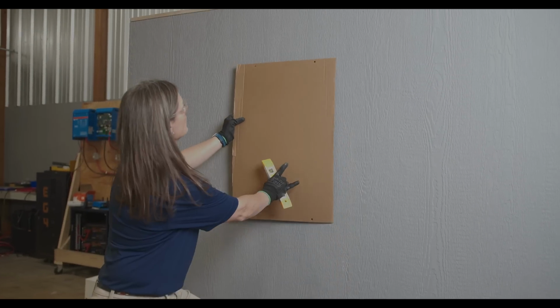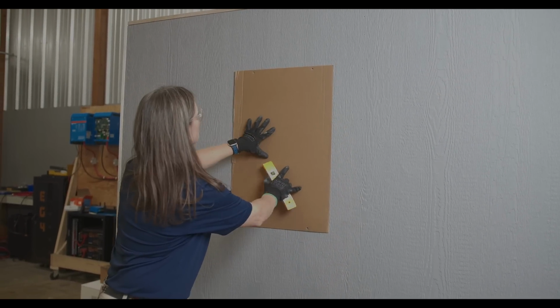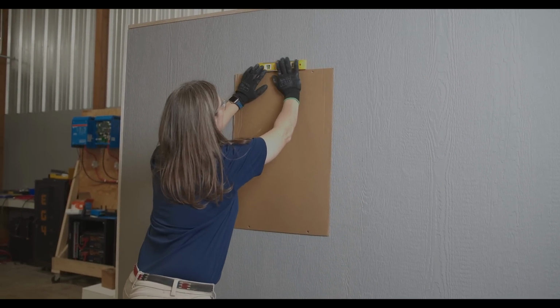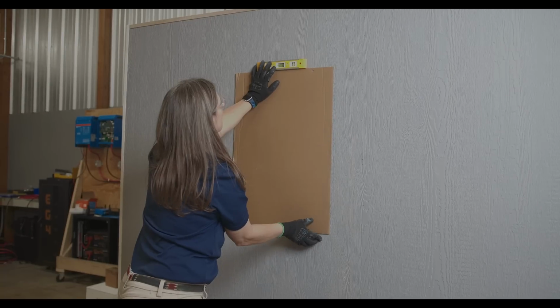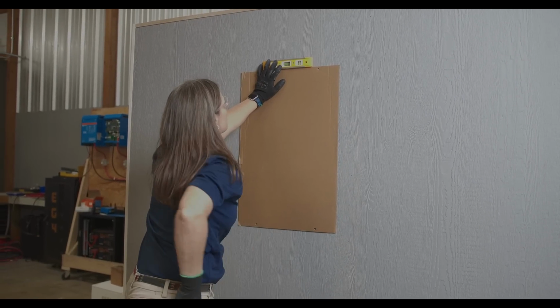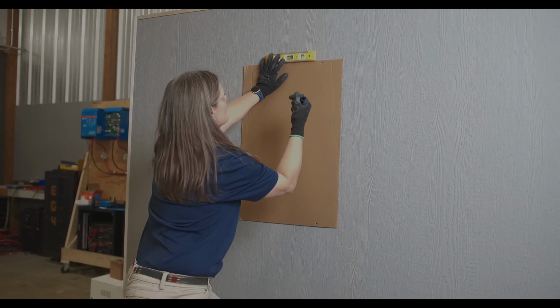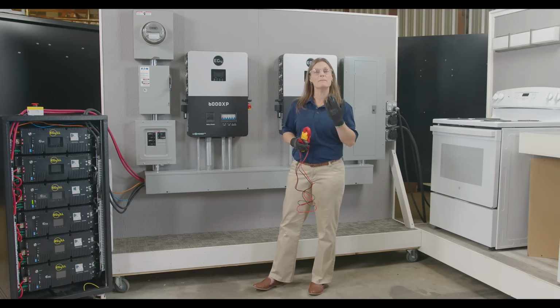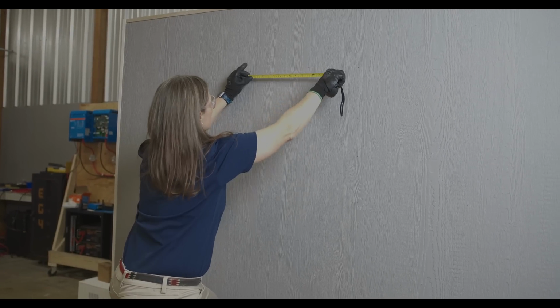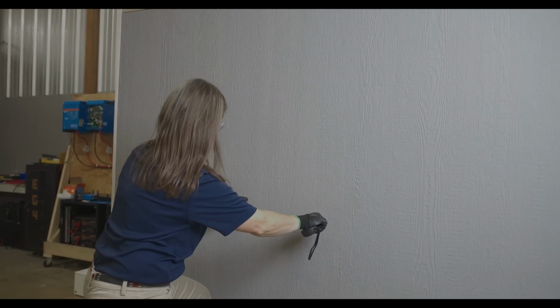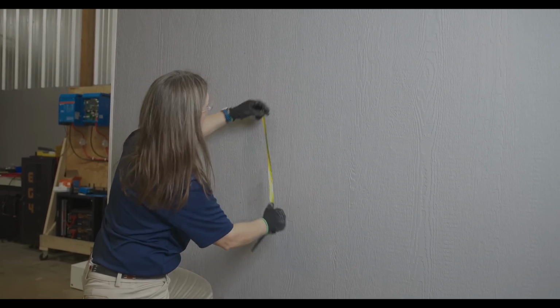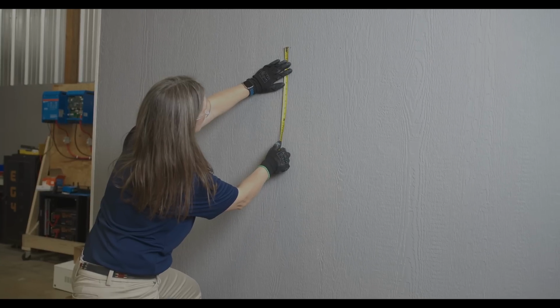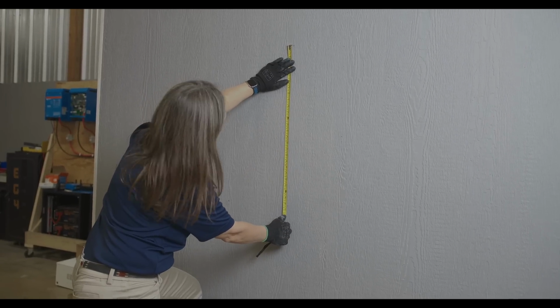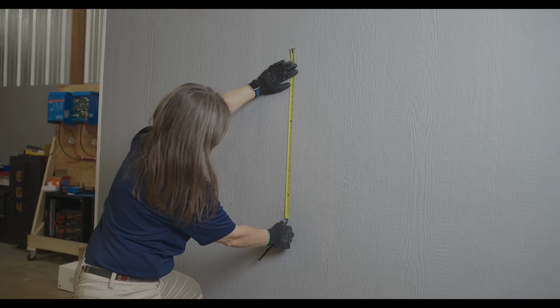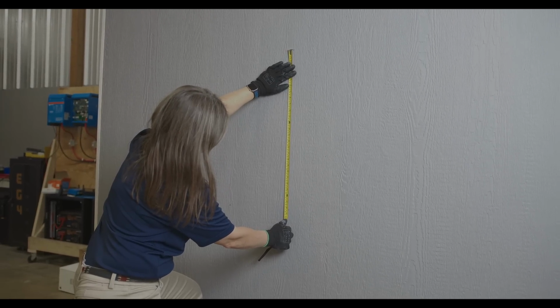Let's take our mounting template. It looks a lot like packing, but this piece of cardboard will help you be precise in determining where your screws will be installed. Check with a level before making your marks. I was always taught, measure twice, cut or drill once. So let's double check those measurements. Your marks should be spaced approximately 10.63 inches horizontally and 26.4 inches vertically. You may even want to hold the inverter up to your holes to make sure they align perfectly.